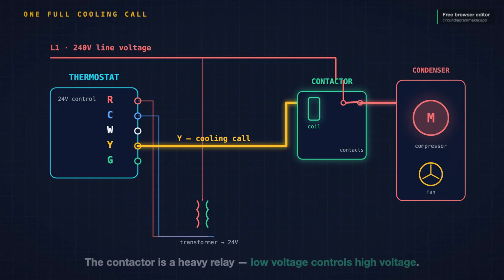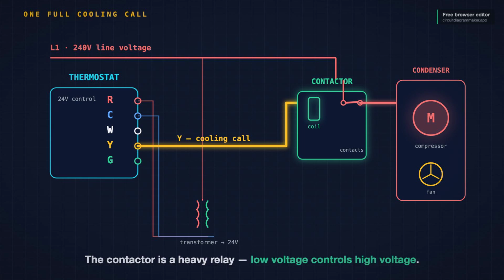That is the sentence to remember. Low voltage controls high voltage. A tiny 24-volt signal, safe enough to run behind your wall, throws a switch that commands a compressor. If you have seen my video on wiring a relay, an HVAC contactor is the exact same idea, just built heavier. Let's make that concrete, live in the browser.